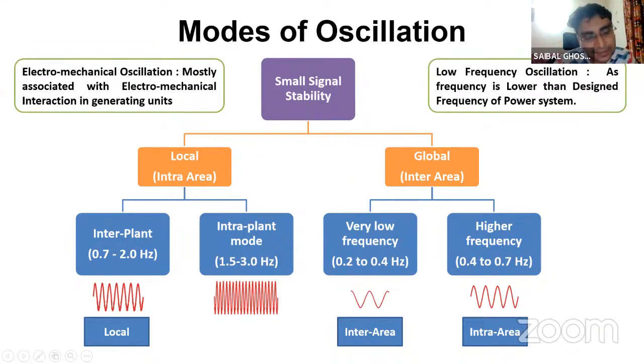On one side there is an infinite grid, and on the other side a single machine. That's why this frequency is a little less. But in the intra-plant mode, this oscillation is not seen outside the plant at all, it is completely inside the plant. If you look at the power exported from the overall plant, there will be no oscillation. Here, oscillation is purely between two units inside the plant.